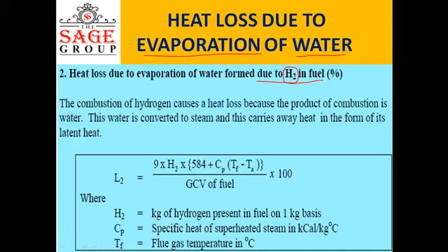So the combustion of hydrogen causes a heat loss because the product of combustion is water, and this water is converted into steam, and this carries the heat in the form of latent heat, because water will change its phase from the liquid phase to vapor phase. So definitely it will take heat in the form of latent heat.